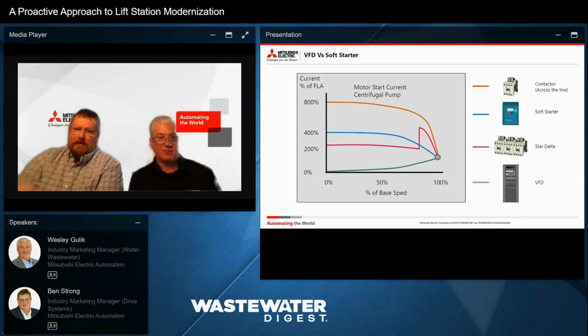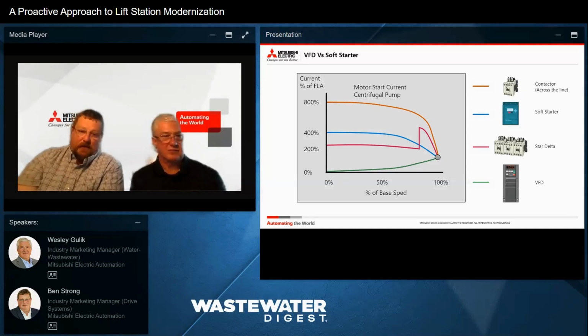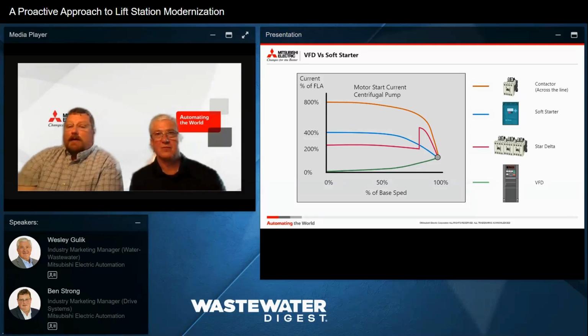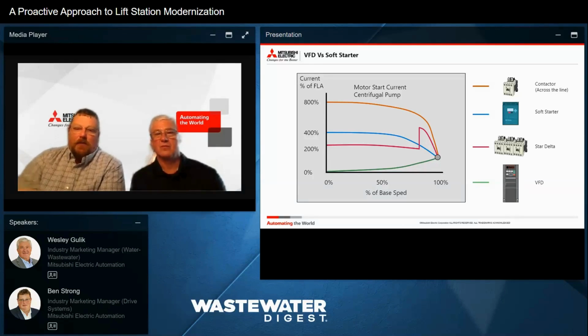And if you look here at this curve, you can see when I'm starting this pump across the line with the contactor, how much current of the motor's rated full load amps is going to draw. And so that's why we created soft starters. We don't want this huge jerk. We don't want the motor to take all this power instantaneously to try to accelerate to 60 hertz. So we use soft starters, and it's a little better. We don't have as much starting current. We don't have as much information about how the motor is operating. But the best choice is using a variable frequency drive.